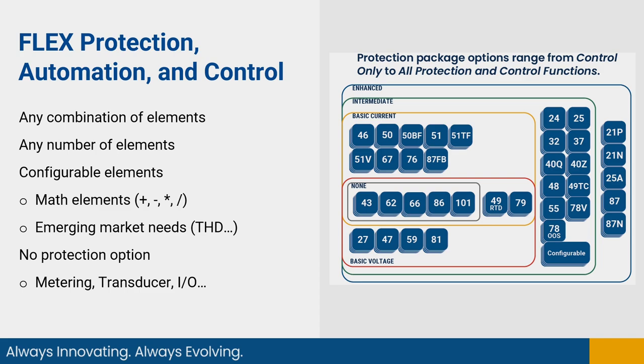So for the protection packages, the Flex provides automation and control, a combination of any number of configurable elements with basic math functions, harmonic elements with total harmonic distortion, and a no protection option. As you can see in the graphic, there is the no protection option, which gets you 62 timer virtual switches and some other items you can use. Then you can go to the basic current from there, or the basic voltage.